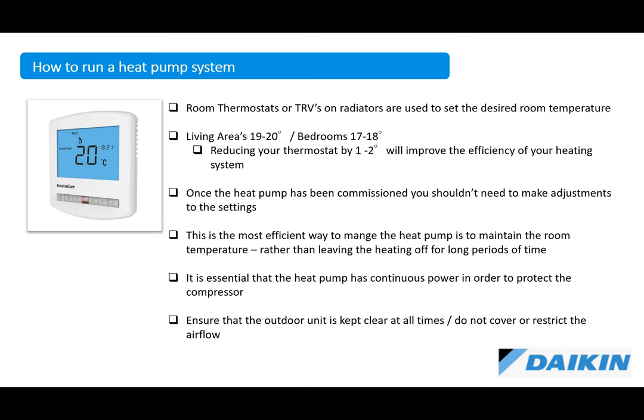So once your heat pump is commissioned, you shouldn't really need to make any adjustments to the settings on the heat pump. If your heat pump is commissioned by a commissioning engineer, they will go in and set up what we call a weather compensation curve. And this is by far the most efficient way to run your heating system. A weather compensation curve takes the outdoor temperature into consideration when it's giving the flow temperature into your radiators or underfloor heating. And it can fluctuate by plus or minus 5 degrees in most cases.